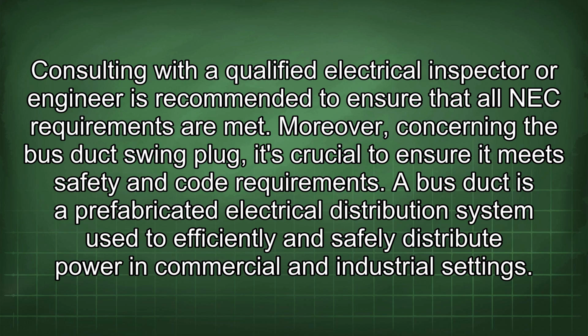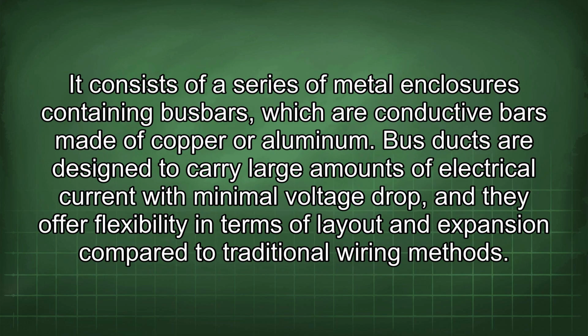A bus duct is a prefabricated electrical distribution system used to efficiently and safely distribute power in commercial and industrial settings. It consists of a series of metal enclosures containing busbars, which are conductive bars made of copper or aluminum. Bus ducts are designed to carry large amounts of electrical current with minimal voltage drop, and they offer flexibility in terms of layout and expansion compared to traditional wiring methods.